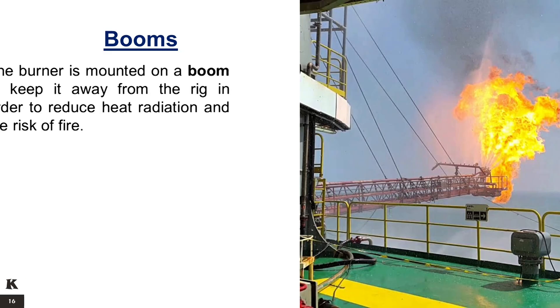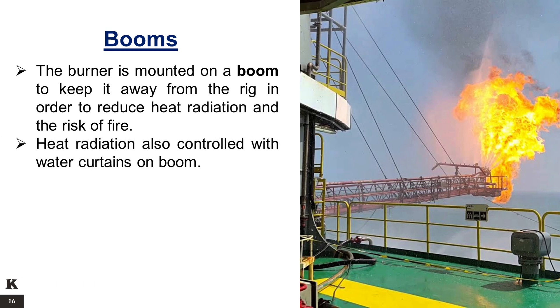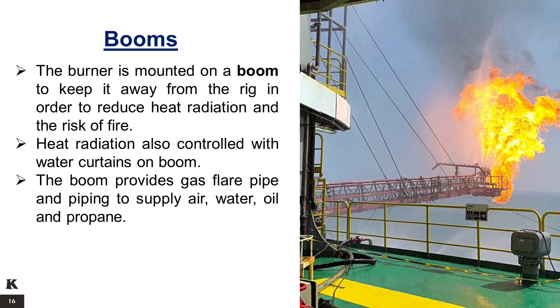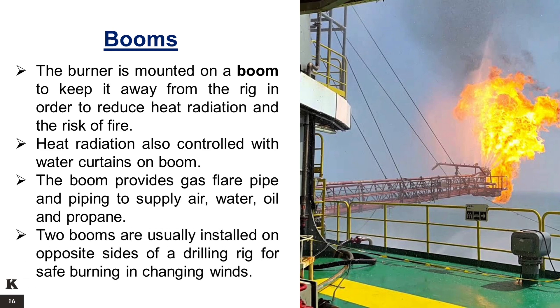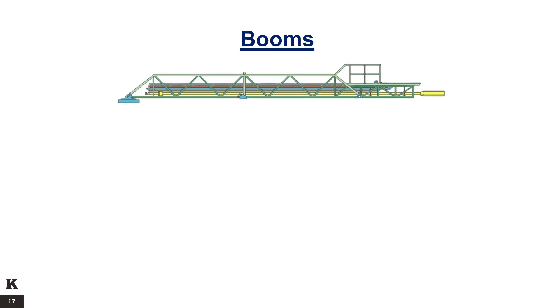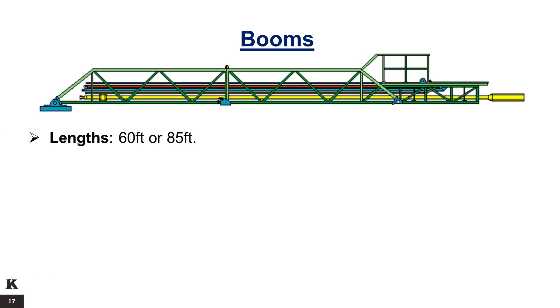Booms. The burner is mounted on a boom to keep it away from the rig in order to reduce heat radiation and the risk of fire. Heat radiation is also controlled with water curtains on the boom. The boom provides gas flare pipe and piping to supply air, water, oil, and propane. Two booms are usually installed on opposite sides of a drilling rig for safe burning in changing winds. Booms exist in 60-feet or 85-feet lengths, with two types of structures available: the U-shaped or the V-shaped.